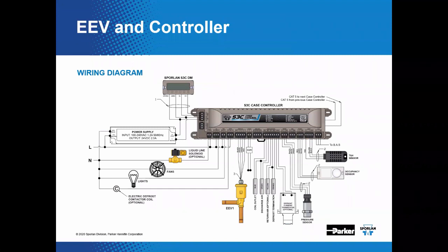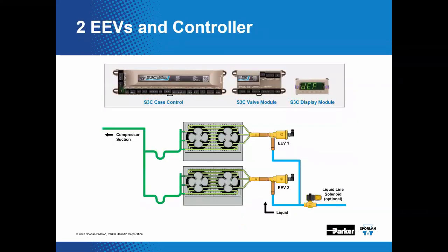You like that? A relatively simple wiring diagram for this method of temperature control. Note the power supply, the display module, the liquid line solenoid valve, the EEV, all these temperature sensors, the pressure transducers hiding over here right there, and of course the case controller itself. And it's going to take inputs and control things like fans, lights, the defrost contactor, and so on. Pretty neat. In this example, the case controller and one valve module are required.